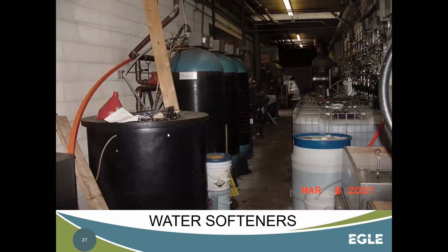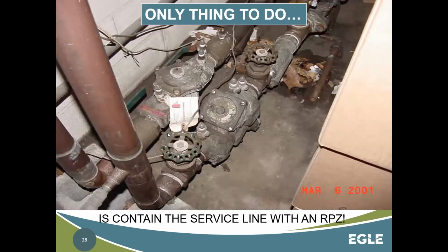So as we can see from this picture, there's a lot going on with this car wash. Again, we have our chemical dispensers with all these tubs or barrels of chemical below them. We were seeing where we had the sinks. We wanted to worry about submerged inlets. We've got some water softening taking place. So what they ended up doing with this property, and the decision you'll have to make, is they just put RPZs right there with the service line coming into the business.